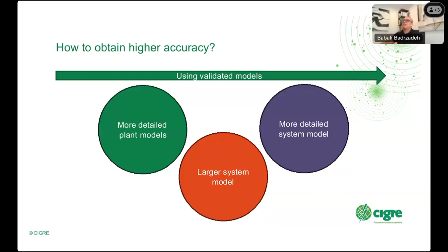Now, these are some of the aspects that will help us decide on using phasor domain versus EMT simulation. For example, what is the phenomenon we are looking for? If we are talking about a phenomenon with a dominant frequency of, let's say, 20 Hertz or 200 Hertz, that is a clear indication we should be using EMT simulation. Whereas a phenomenon close enough to the system fundamental frequency, or a slow enough phenomenon, phasor domain simulation may still be valid.